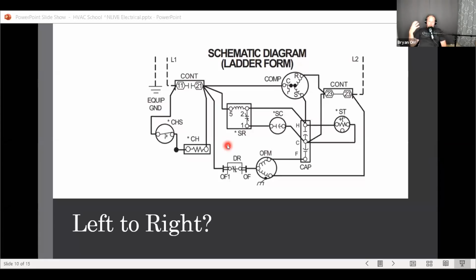It'll actually, in a lot of cases, take out a transformer before it even takes out the fuse. It's a weird thing about the transformers we work on, because the transformers we use are 40 VA, which means that if you take 40 divided by 24, they're rated for about 1.66 amps, but yet we put 5 amp fuses on them. So when you have cases where you've got a coil or something that's not engaging properly and it's drawing 3 amps or something like that, it's not going to blow the fuse in a lot of cases. It'll just take the transformer out on you. But anyway, just a side note there.